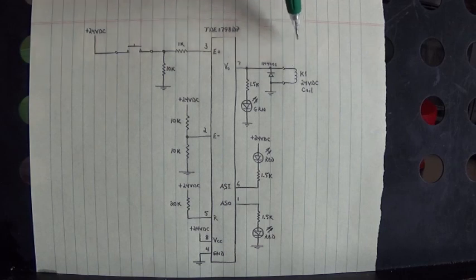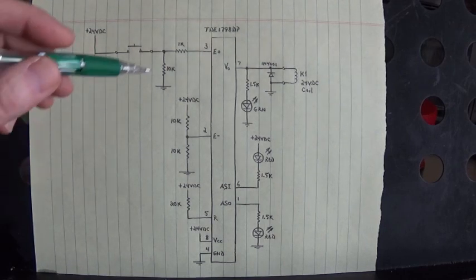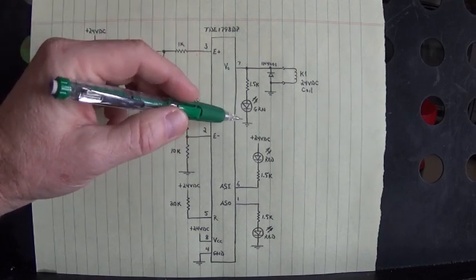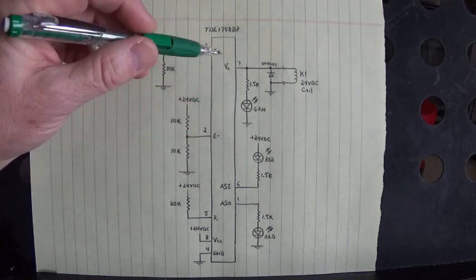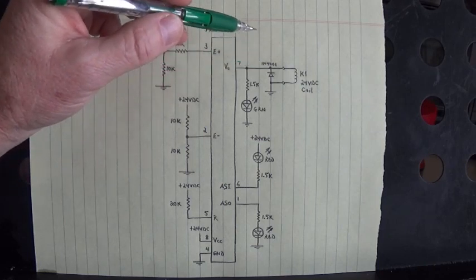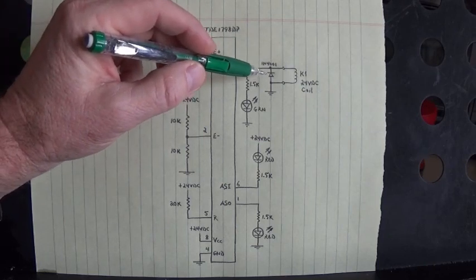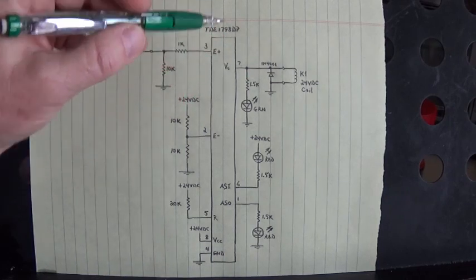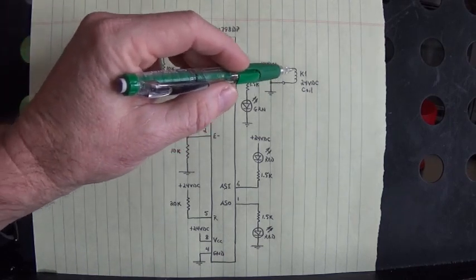I don't show the contacts, just the coil. Here's the green LED that indicates the output is turned on right there. This is the spike suppression diode - you always want to have a spike suppression diode when you're turning on a DC relay coil.